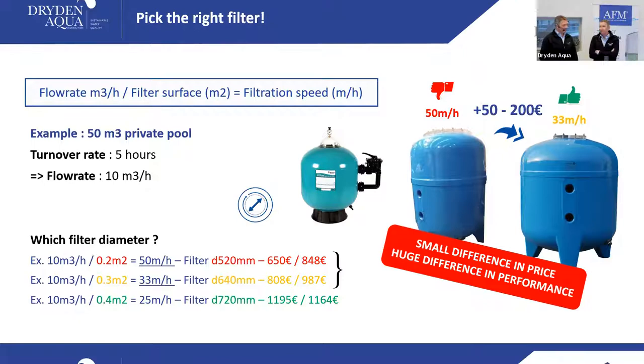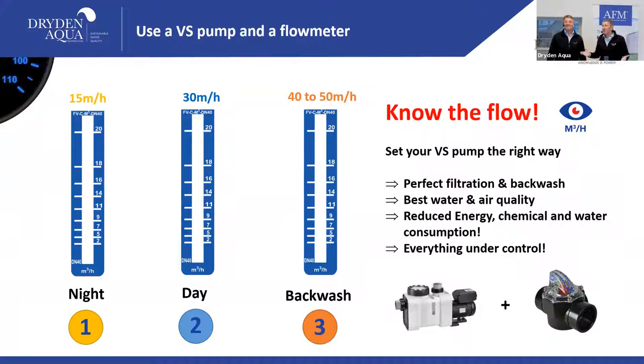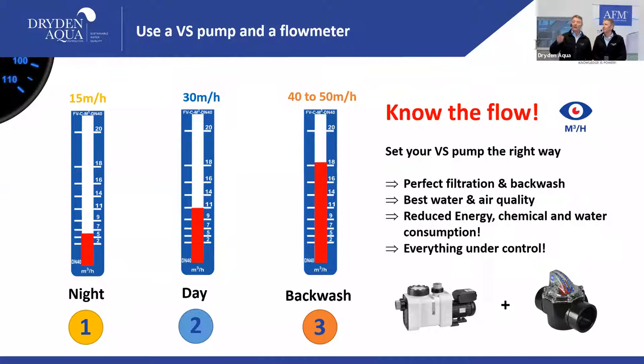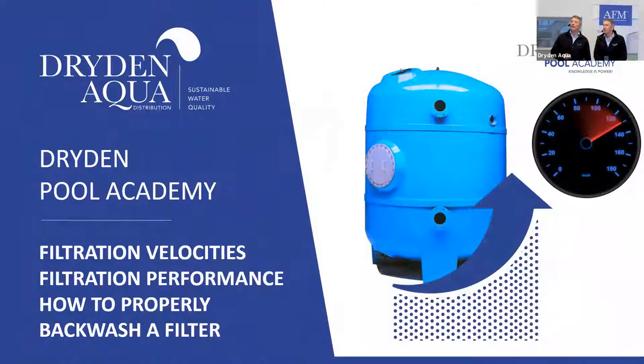Knowing your flow rate is key — it lets you set your variable-speed pump precisely for day, night, and backwash modes. Always use a flow meter; ideally a FlowVis for variable-speed pumps.